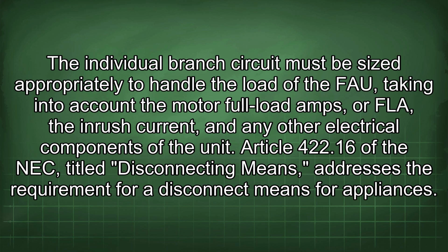The individual branch circuit must be sized appropriately to handle the load of the FAU, taking into account the motor full load amps, or FLA, inrush current, and any other electrical components of the unit.